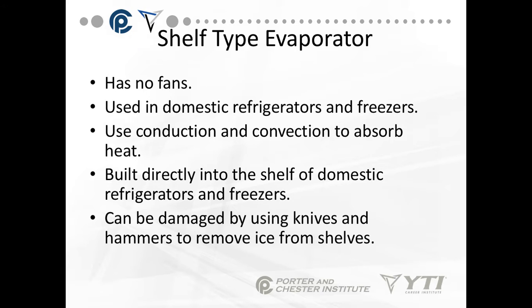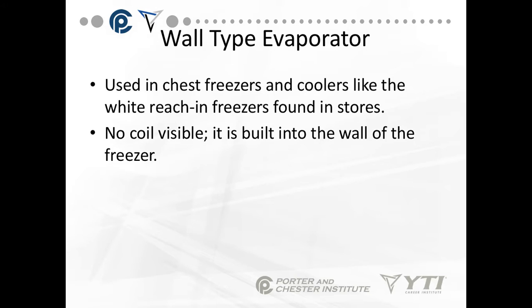The shelf type evaporator also has no fans. It's used in domestic refrigerators and freezers, primarily freezers, and uses conduction and convection to absorb heat. It's built directly into the shelf, and it's very frequently damaged by homeowners using knives and hammers to remove ice instead of defrosting. The wall type evaporator is used in chest freezers and coolers like white reach-in freezers found in stores — there are no visible coils, as the coil is built into the wall of the freezer.